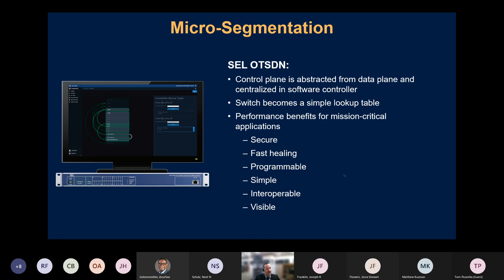As an SEL employee, I want to mention one of our pieces of technology that I work with a lot and think really does help simplify our networks. Like traditional SDN, the control plane is abstracted from the data plane. We have the ability to be very specific about what we allow on our network. Even if IPv6 and those types of services haven't been configured on individual devices, they won't pass in this switch. We have to be incredibly specific and understand what host-to-host communication looks like, so we deterministically design the network and move traffic between endpoints.